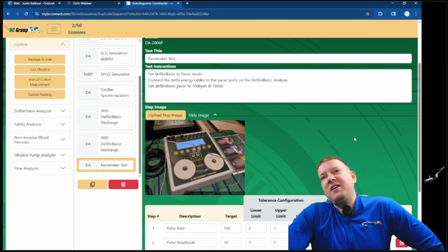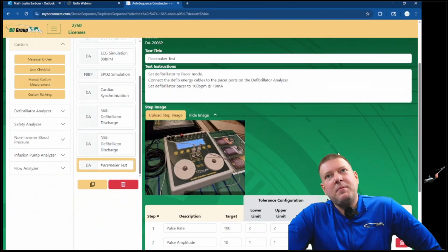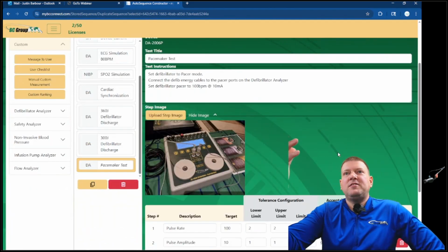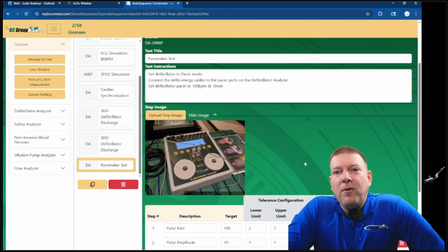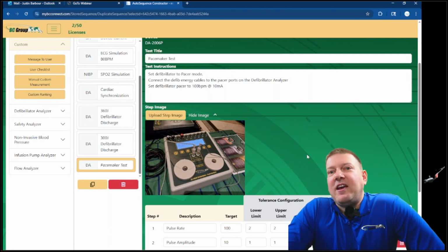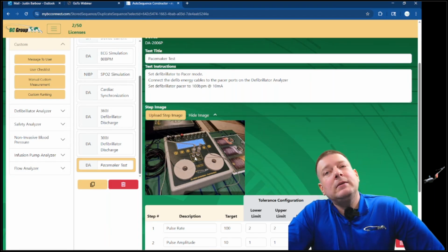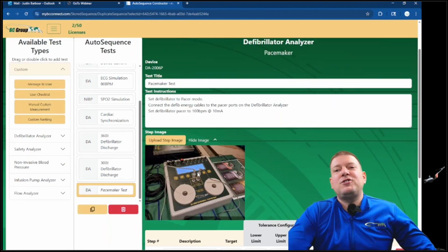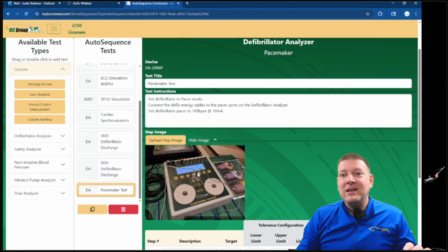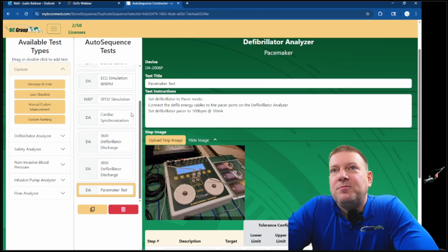And pacemaker tests. Okay, this is the last one I'm going to show you guys when it comes to setting up a test. People make this mistake. I made this mistake. I mean, all the time. Defib analyzers often have a separate port for testing pacing. I incorporated an image here to show them. If you're testing pacing, move your cables to these ports.